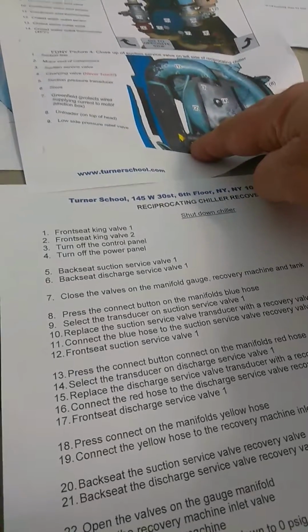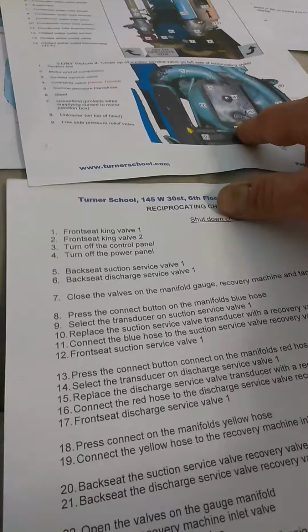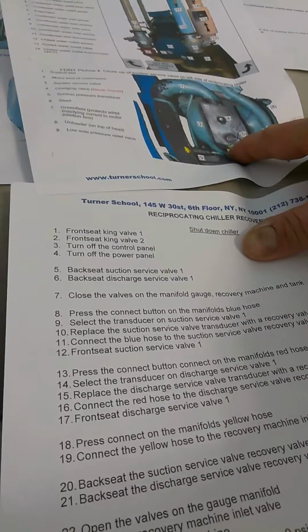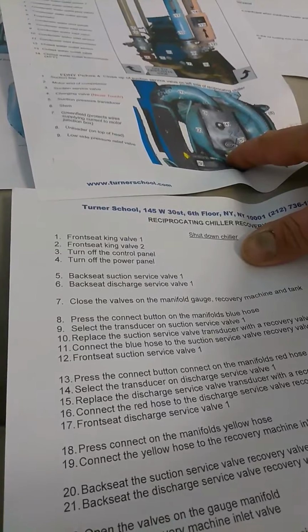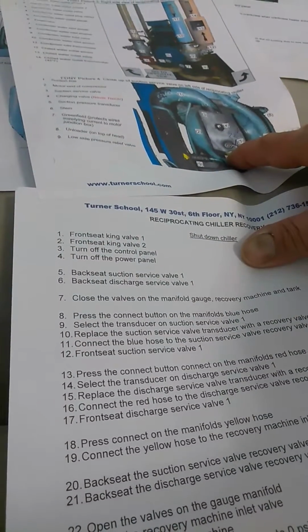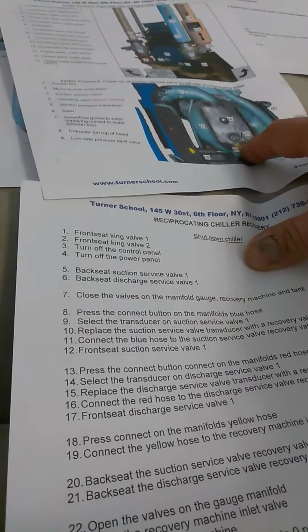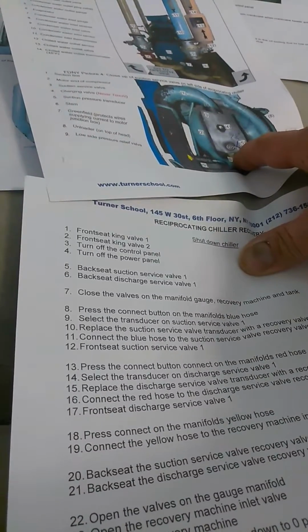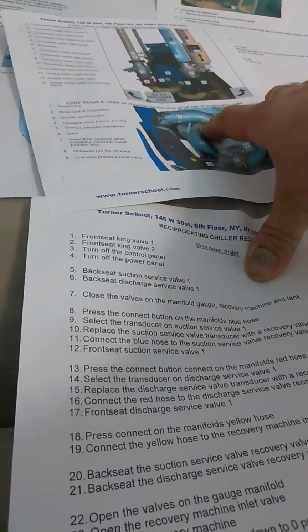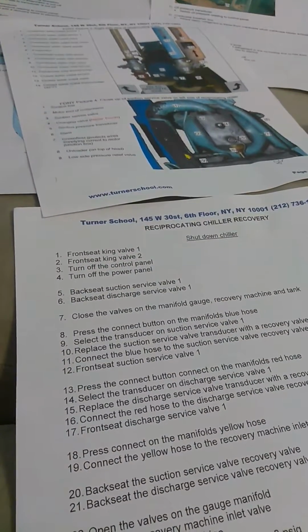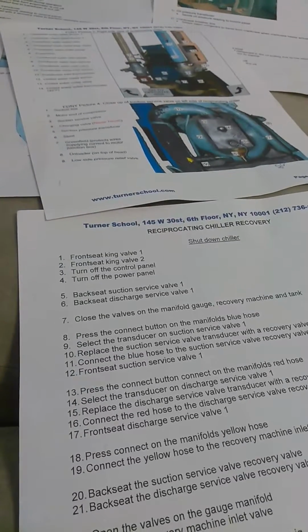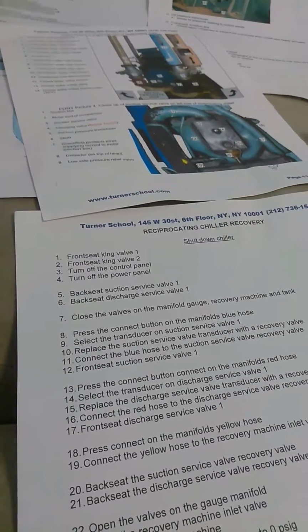Alright, then you go to your gauges. Connect the blue. And you go over here. Select the transducer on the suction service valve. Okay, and replace it with the recovery valve. And then you connect the blue hose to the recovery valve and you front seat suction service valve. And you go to the red. Blue is suction, red is discharge.